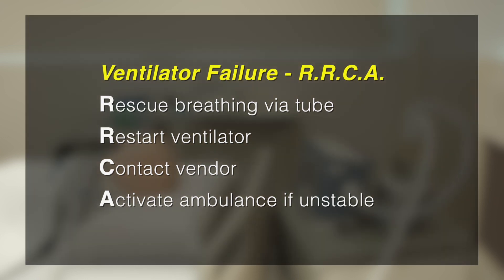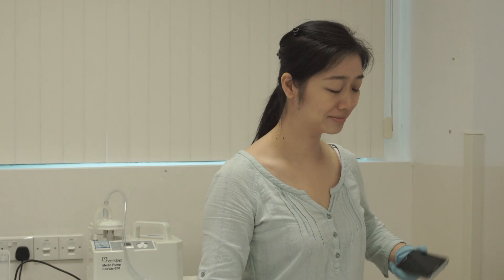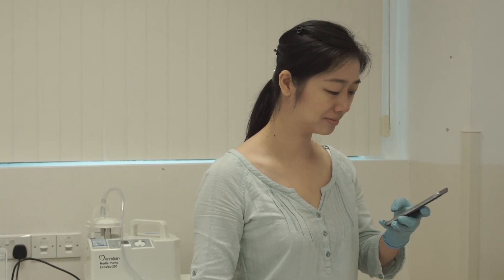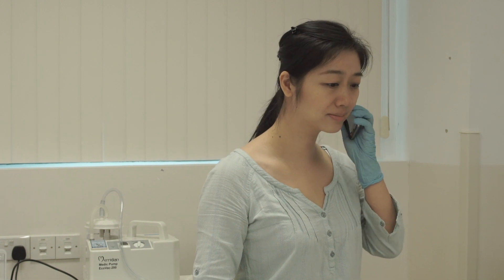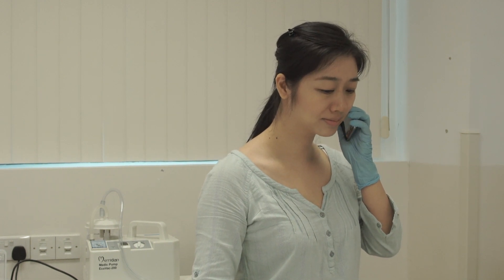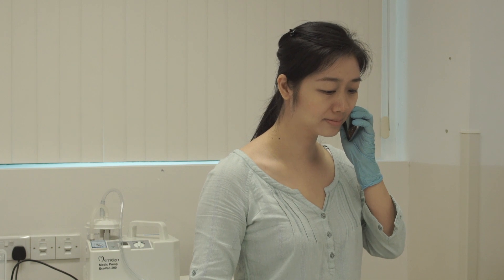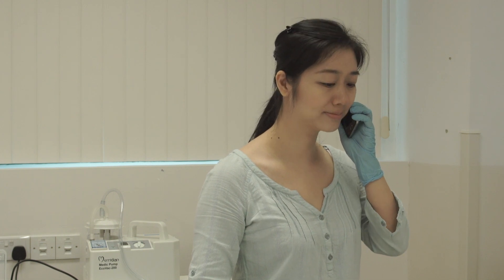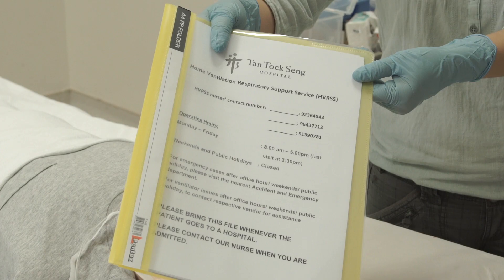C is for contact the vendor. Contact the vendor for a replacement machine, even if you have successfully restarted the ventilator. Your vendor should be able to retrieve the settings from the faulty machine. You may also refer to your home file for the latest settings.